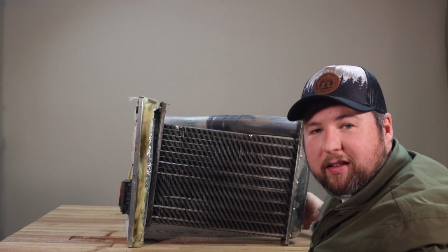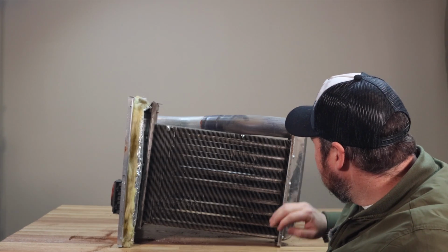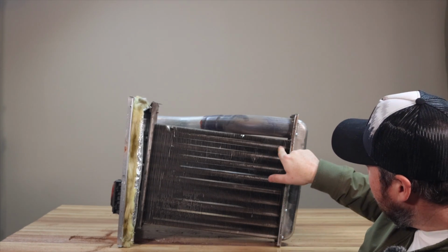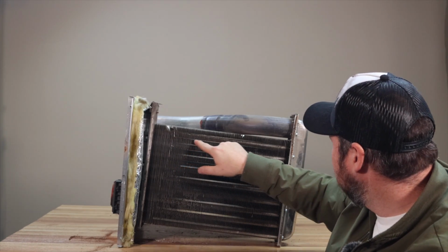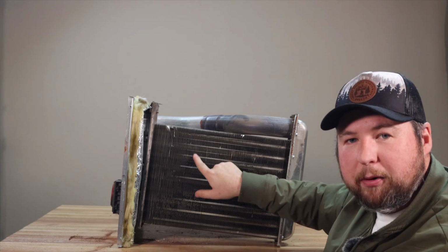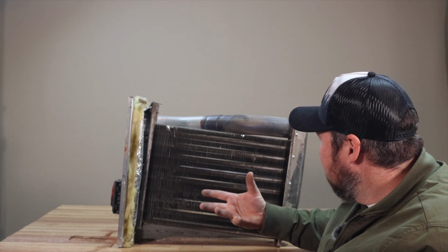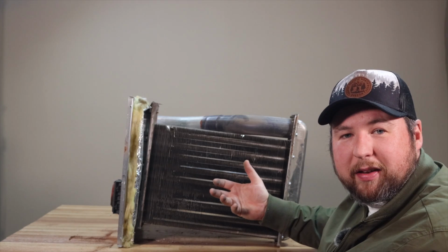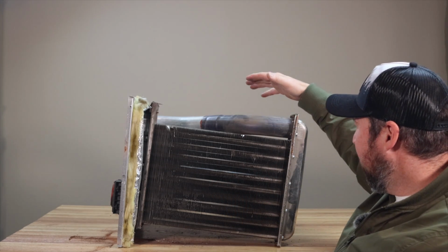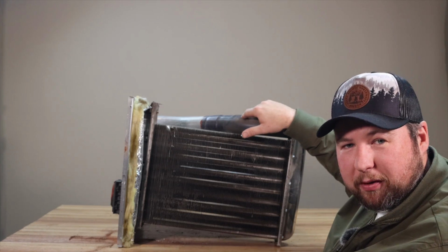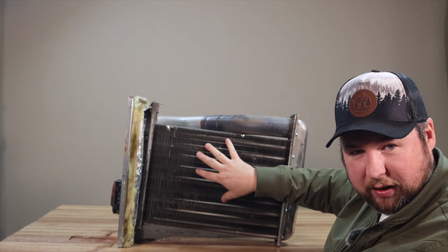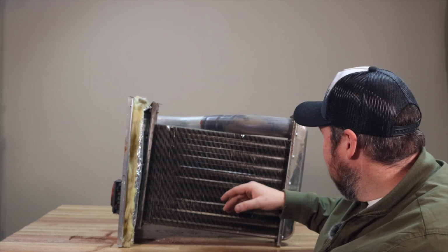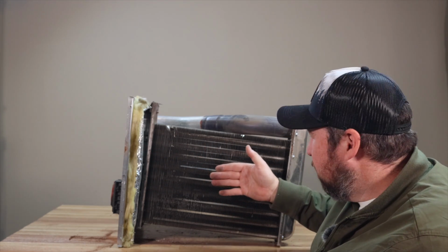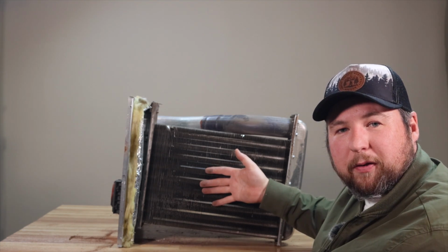Or you could call it a condenser because it's a condensing heat exchanger. So in here you can see you have a bunch of little tiny tubes, and then they put fins on it to expand that surface area to maximize heat transfer. So whatever heat is left over after the primary, the secondary heat exchanger is going to suck up the last of it, by squeezing it into smaller tubes and maximizing your surface area.